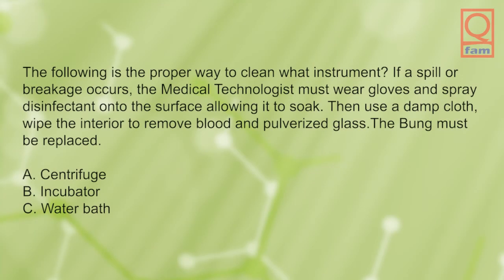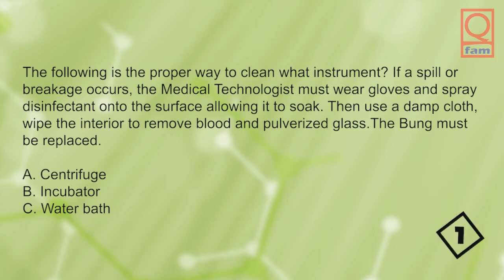The following is the proper way to clean what instrument? If a spill or breakage occurs, the medical technologist must wear gloves and spray disinfectant onto the surface allowing it to soak, then use a damp cloth to wipe the interior to remove blood and pulverized glass. The bung must be replaced. A) centrifuge, B) incubator, C) water bath. The answer is A, centrifuge.